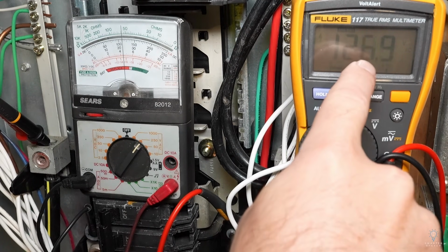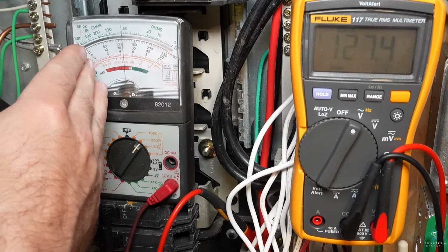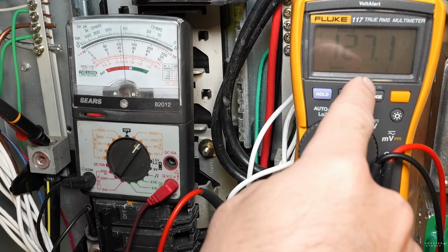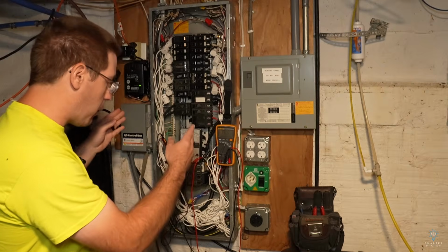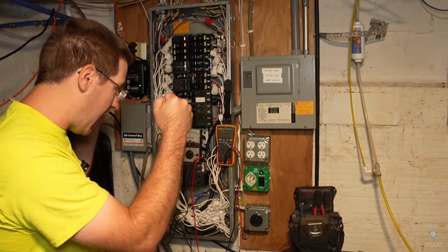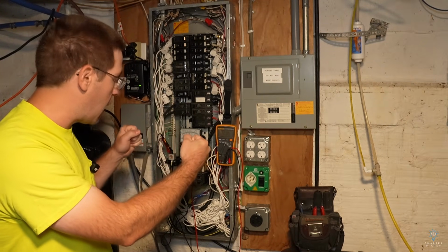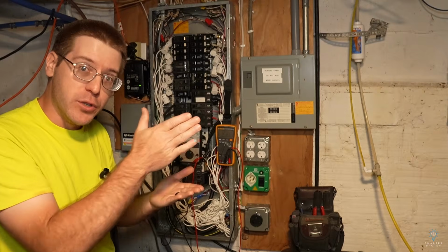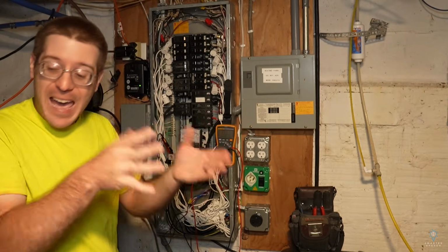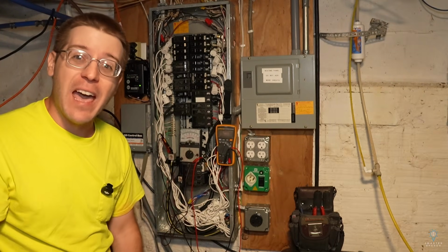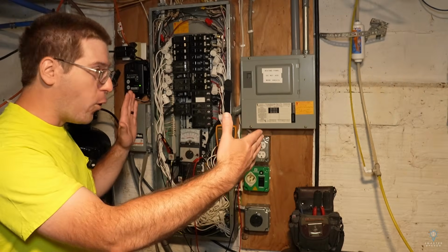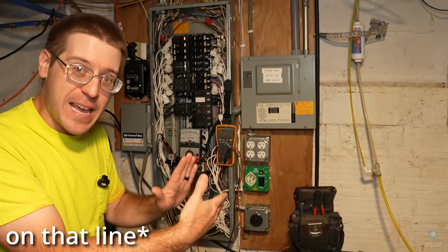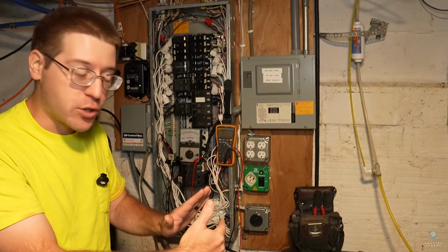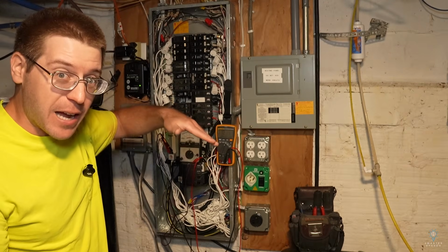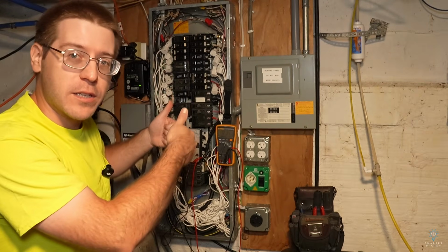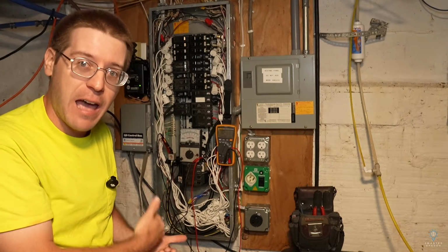See, now this voltage spiked and this voltage dropped. So this went up about 5 more volts and this dropped 5 volts. Our 2 lines are staying solid. We've got 240 volts between our lines, but it is that reference point to neutral that keeps moving as the load changes. So the heavier the load, the more voltage drop we get on that phase. So the heavy load gets the voltage drop, which means it tips the teeter-totter and boosts the voltage on the second line that doesn't have as much current.